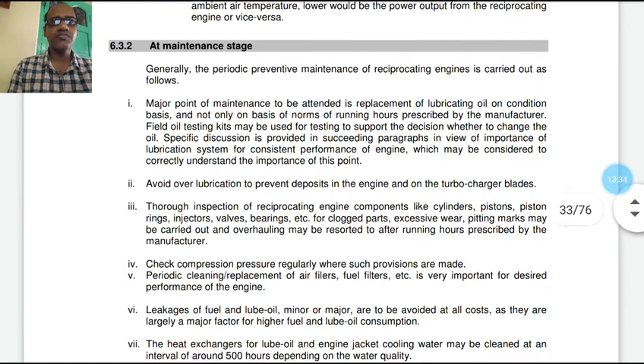Now, at maintenance stage, generally periodic preventive maintenance of reciprocating engine is carried out as follows. The major point of maintenance to be attended is replacement of lubrication oil on condition basis, and not only on the basis of norms of running hours prescribed by the manufacturer. Field oil testing kits may be used for testing to support the decision whether to change the oil. Specific discussion is provided in succeeding paragraphs in view of the importance of lubrication system for consistent performance of the engine, which may be considered to correctly understand the importance of this point.